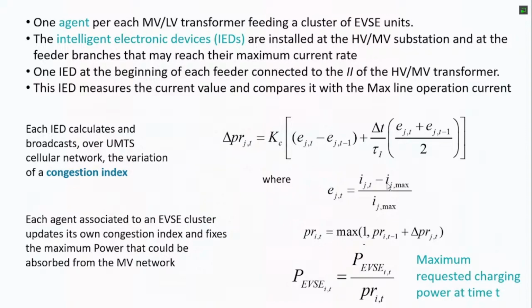This error is a function of the error in the current. If the current is larger than the maximum current, dividing current by maximum gives you the error at this time, and you also take into account the error in the previous time step. There is also an integral part in which the two errors are summed together. So if the error occurs in just one period, you take one decision and reduce the power a little bit. But if it happens again in the second period, it accumulates, so we need to decrease or increase more of this congestion signal.